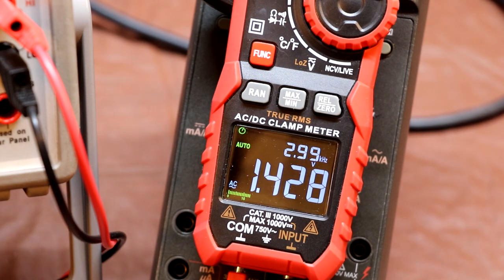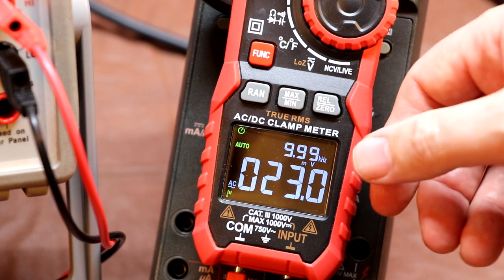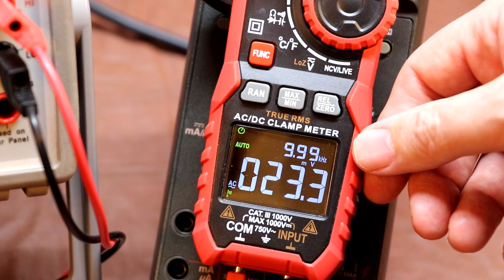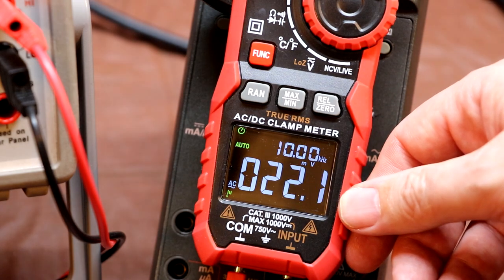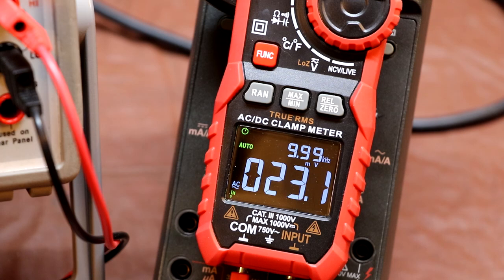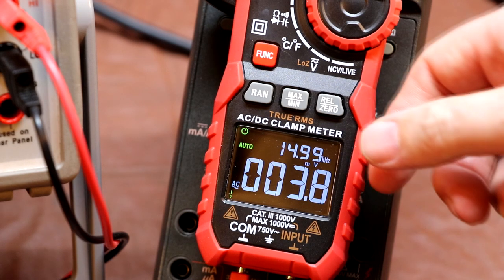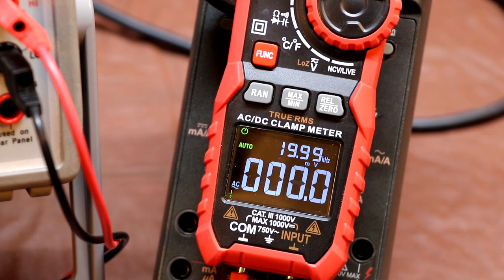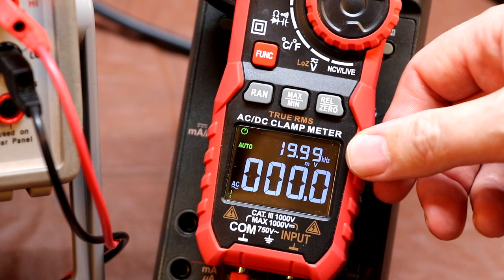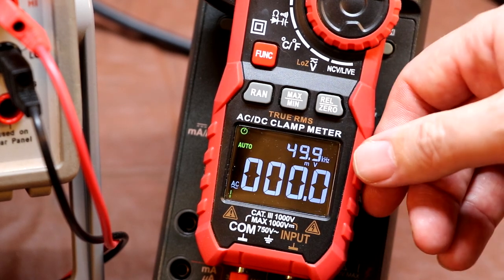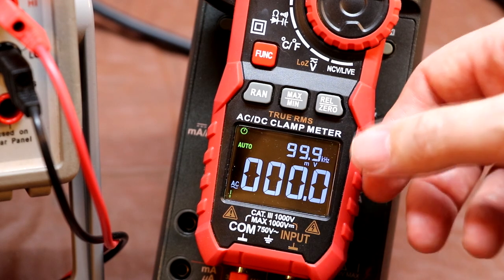And when the voltage mode is selected, the frequency range is between 10 Hz and 10 kHz. As you can see, the frequency reading is correct at 10 kHz, but of course the voltage reading isn't. Let's see what happens if we increase the frequency outside of the meter's specification to above 10 kHz. And at 15 kHz the frequency reading is perfect, and 20 kHz is indicated without any problems. And 50 kHz is also correct, as is 100 kHz.